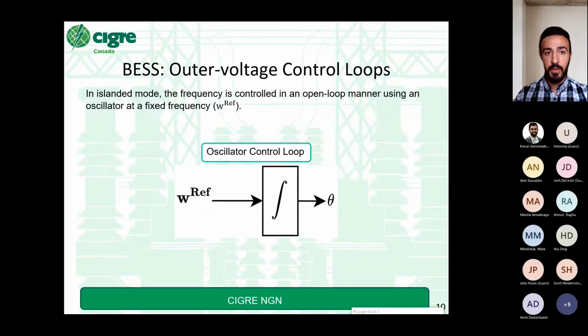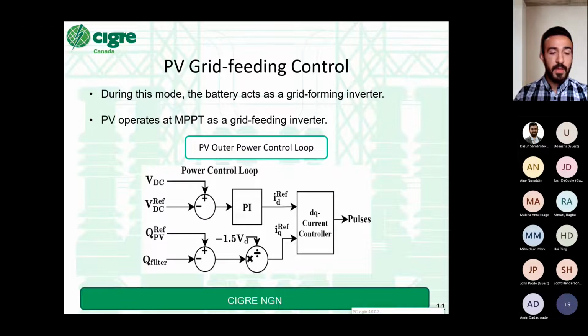Since this is an isolated microgrid, the frequency is going to be controlled in an open loop manner using an oscillator at a fixed frequency. The oscillator diagram is going to look like this. When we operate the PV in a grid feeding control, the battery in such case is mainly responsible for forming the voltage and frequency for the PV VSC. In such conditions, the PV will operate at MPPT most of the time as a grid feeding inverter.